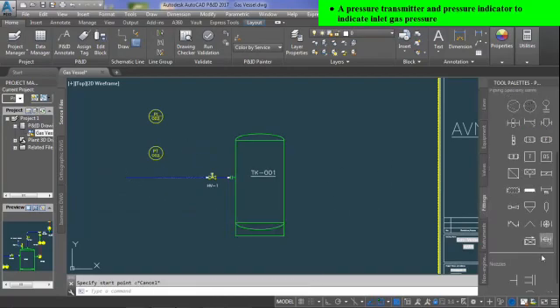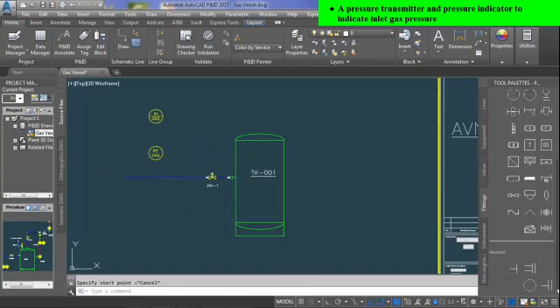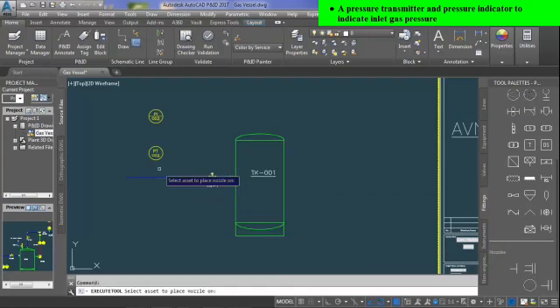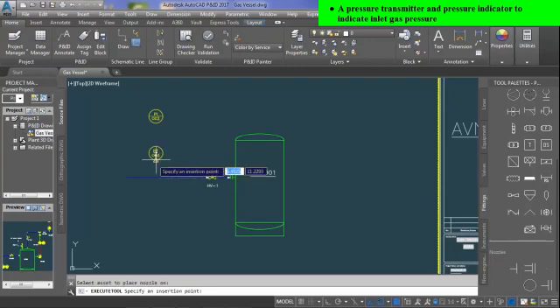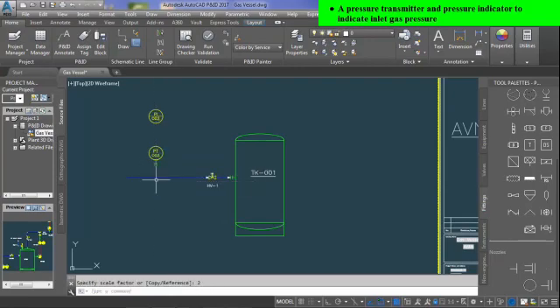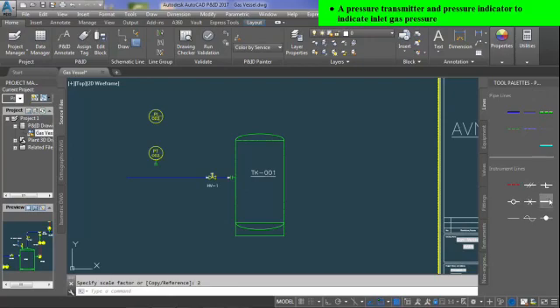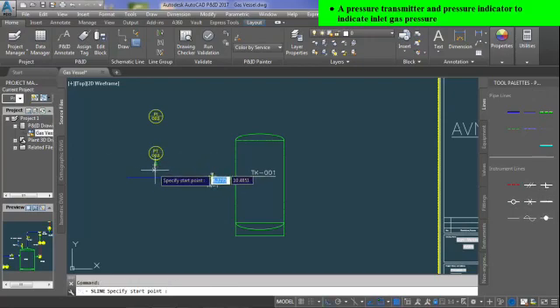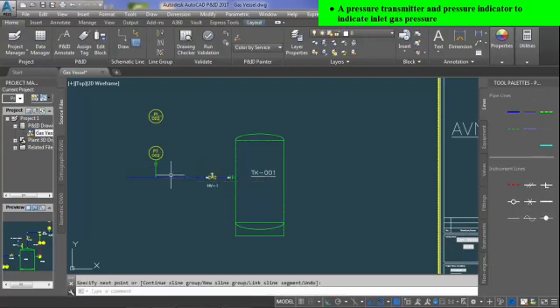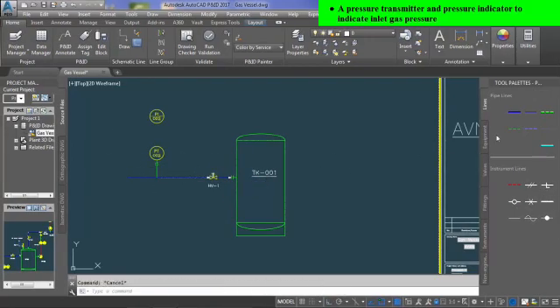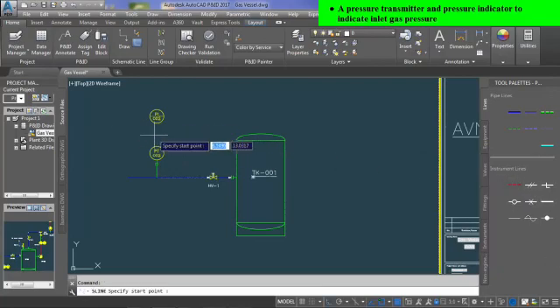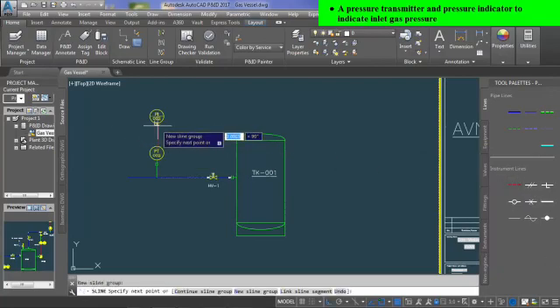Then insert primary pipeline to attach the pressure transmitter. The pressure transmitter is attached with the primary pipeline through a flanged nozzle. From the fittings tab, select the desired nozzle and attach the pressure transmitter to the main pipe with an instrument supply line from the lines tab. After that, draw an electrical line to attach the pressure indicator with the pressure transmitter.